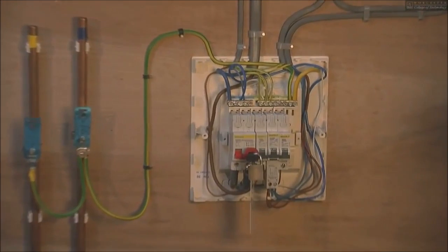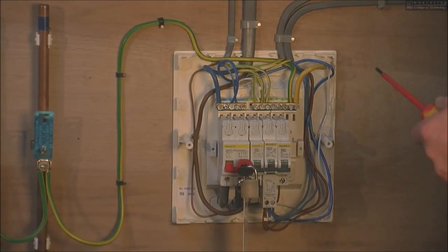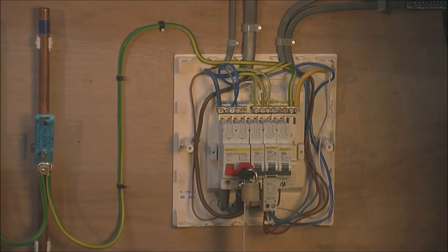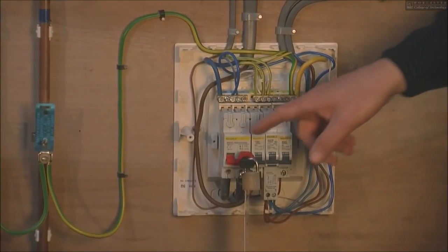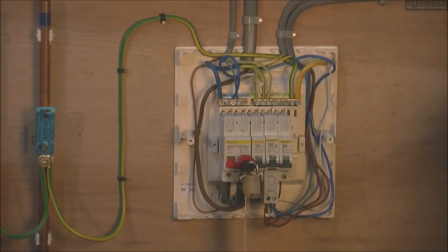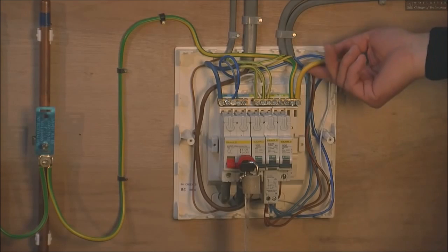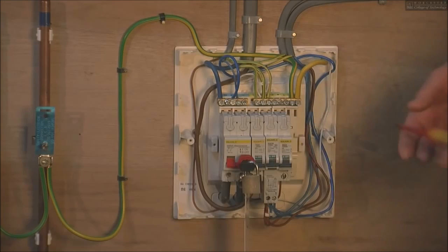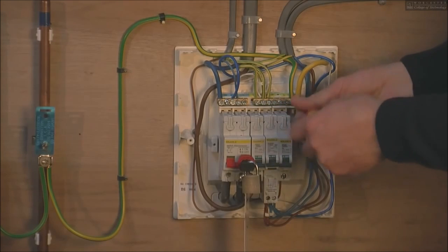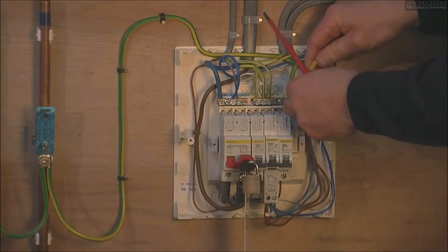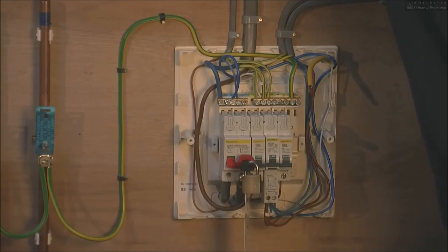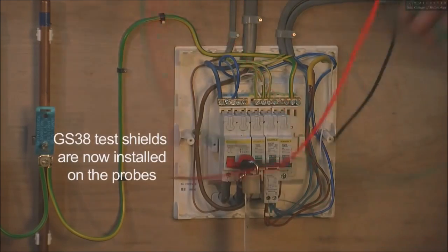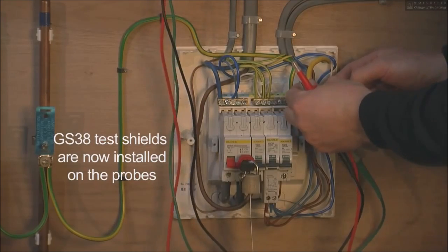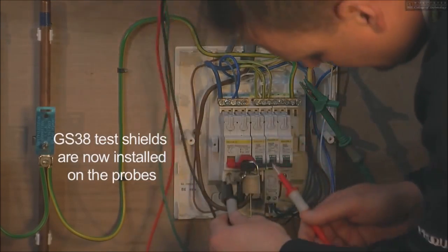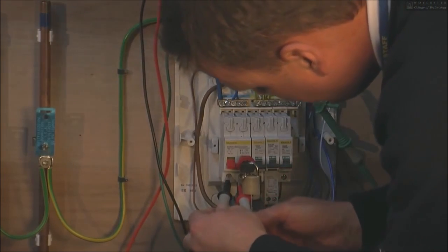We're now going to measure the external earth loop impedance. So firstly we set the tester from the insulation resistance round to the earth loop. We leave the locking device on the fuse board because we're now going to remove the main earth. If we remove this earth and the circuits were energized, then the entire installation would not have any protection. So we remove the main earth like so. We then take our tester, place the crocodile clip onto the earth. Remember to stick the neutral in first, and then finally the line conductor.